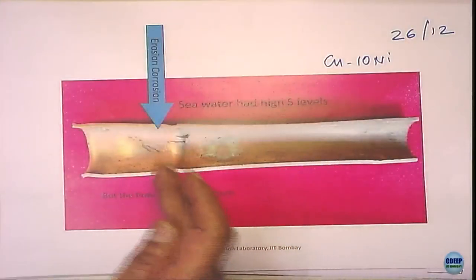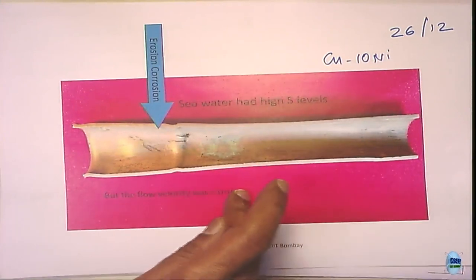Moreover, there is one more problem. If you take sea water and do not use a filter, as you rightly said, about 30% of the tubes were clogged because of some plastic, something happened. When they opened it up, they found these were all blocked. That means only the remaining tubes are operating, so the actual velocity is not just 1 meter per second, it increases further. That adds more complexity to the problem.